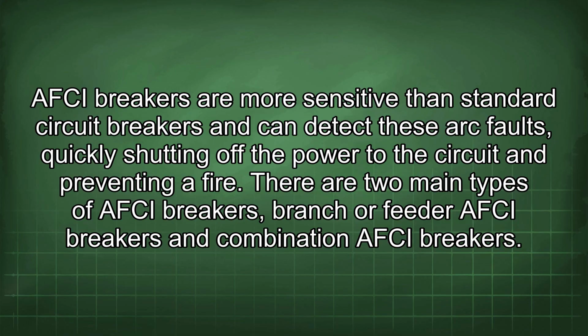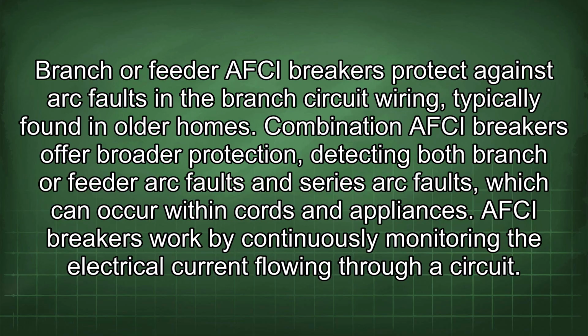There are two main types of AFCI breakers: branch or feeder AFCI breakers and combination AFCI breakers. Branch or feeder AFCI breakers protect against arc faults in the branch circuit wiring, typically found in older homes. Combination AFCI breakers offer broader protection, detecting both branch or feeder arc faults and series arc faults, which can occur within cords and appliances.